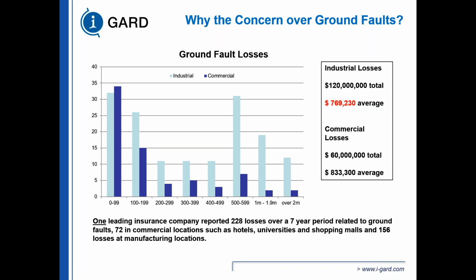When you have a ground fault, typically you have several types of systems: ungrounded systems, solidly grounded systems, resistively grounded systems. Here's one leading insurance company that reported over 200 losses over a 7-year period related to ground faults. So ground faults happen all the time in industrial and commercial systems. 72 of these were in commercial locations such as hotels, university shopping centers, convention centers, and 156 losses from manufacturing locations. The total losses that this one insurance company had to pay out was $180 million.